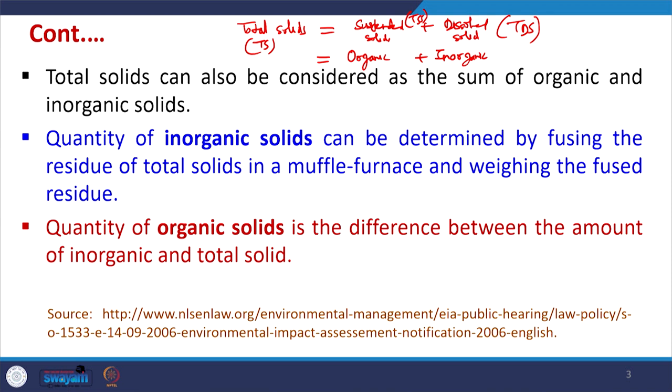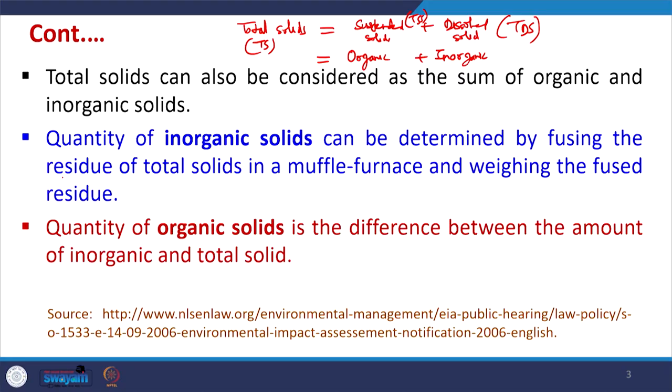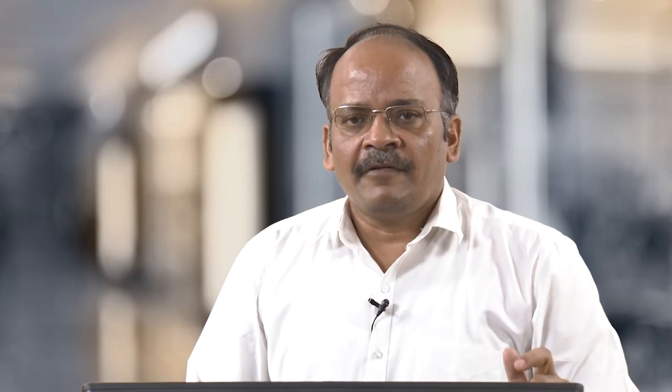The quantity of inorganic solids in any water or wastewater sample can be determined by fusing the residue of total solids in a muffle furnace and weighing the fused residue. First we evaporate the water to get total solids, then we fuse the total solids in a muffle furnace at a specific temperature — the organic content burns off and only the inorganic content remains. By weighing the fused residue we determine inorganic solids, and by the difference between total solids and inorganic solids we can get the total organic solid. This organic solid is highly helpful because it will be easily biodegradable.